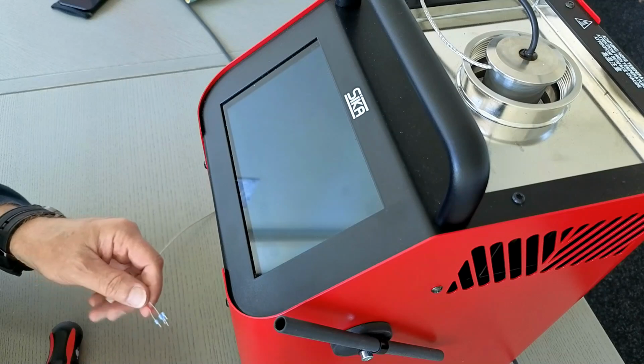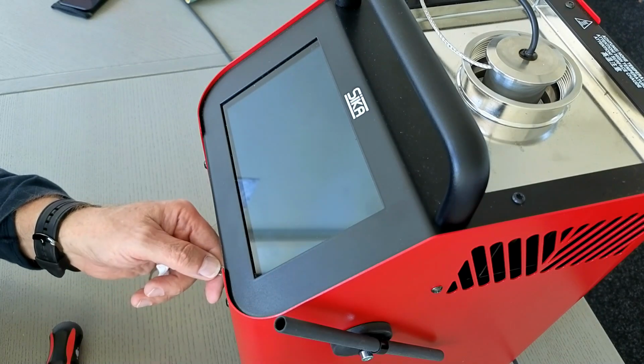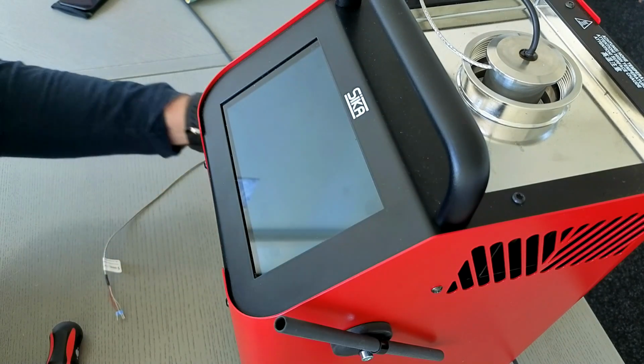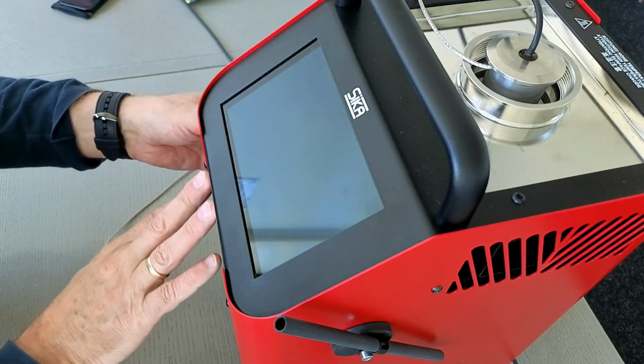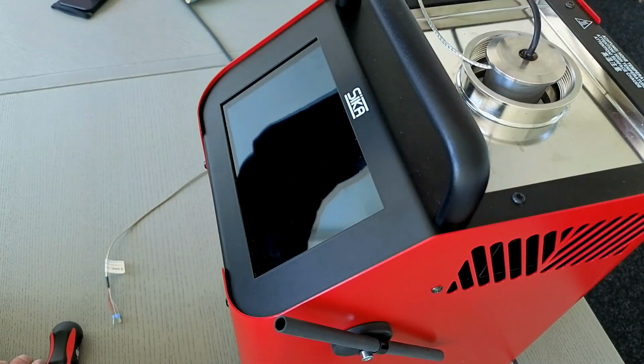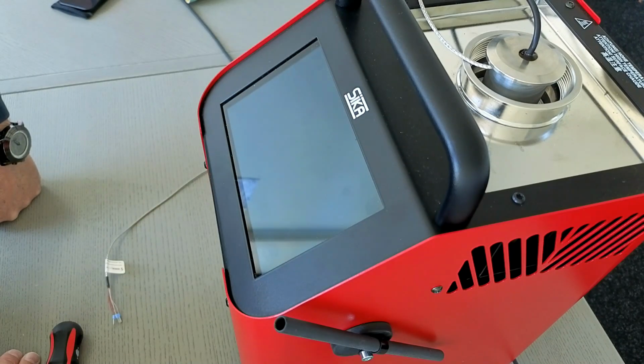Connect the reference sensor to the calibrator on the reference port, and connect your device under test, for example, to the integrated measuring instrument. With this setup, you can perform a calibration of flange temperature sensors.